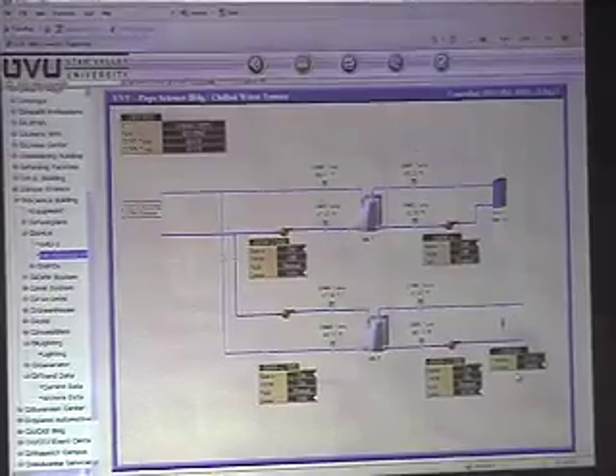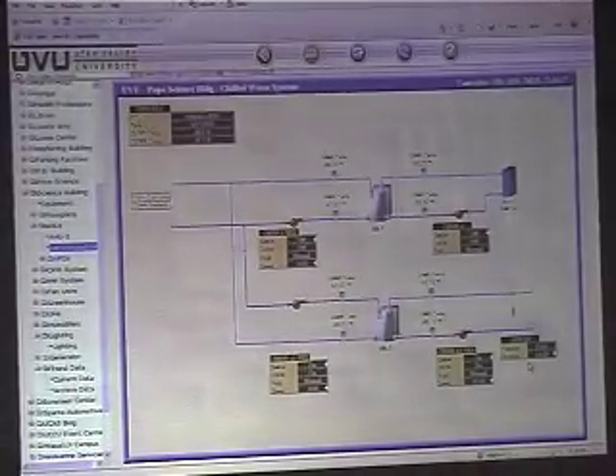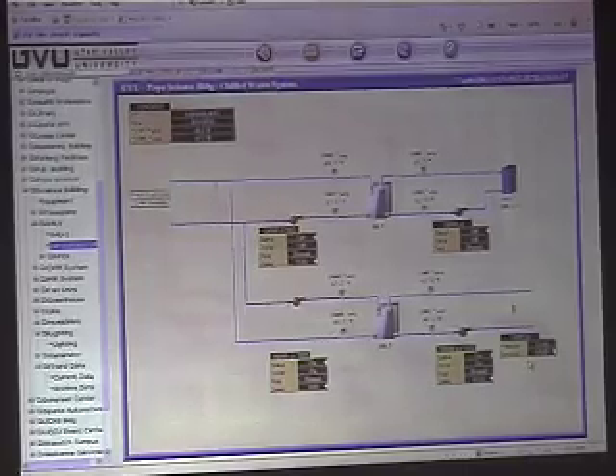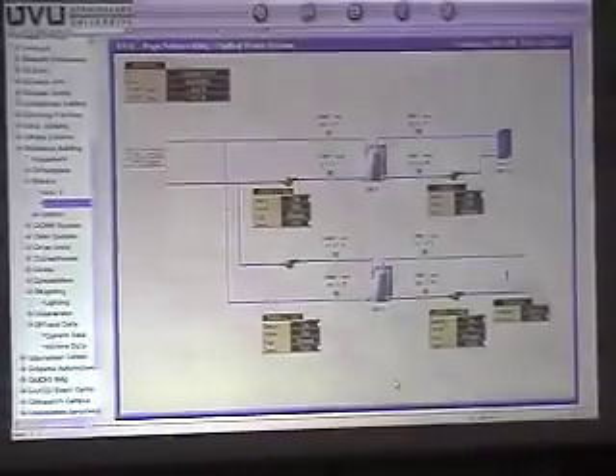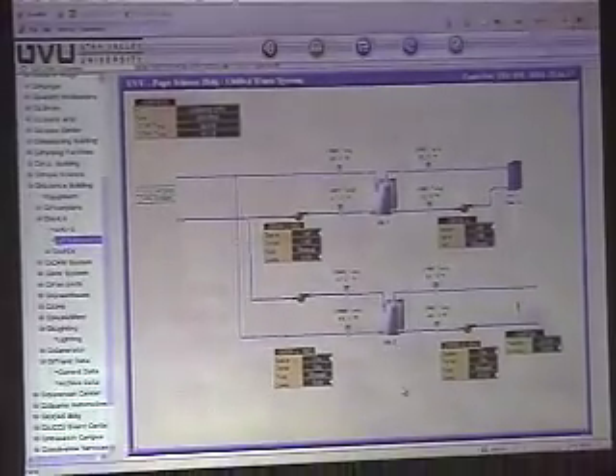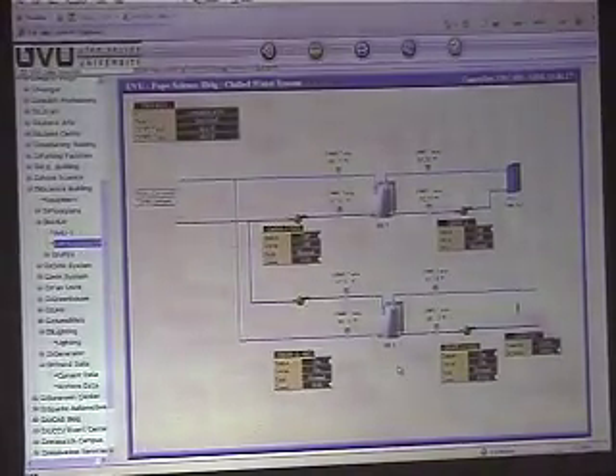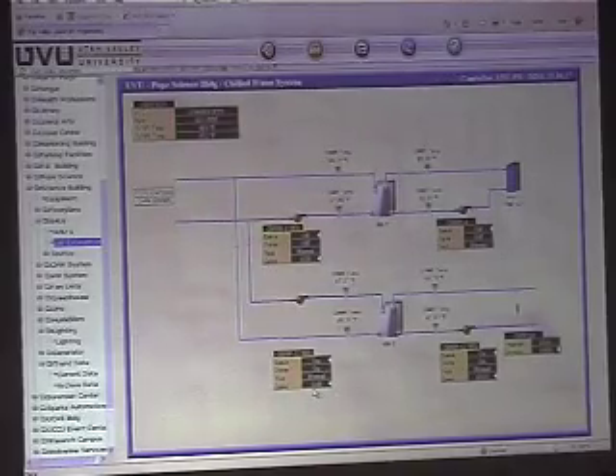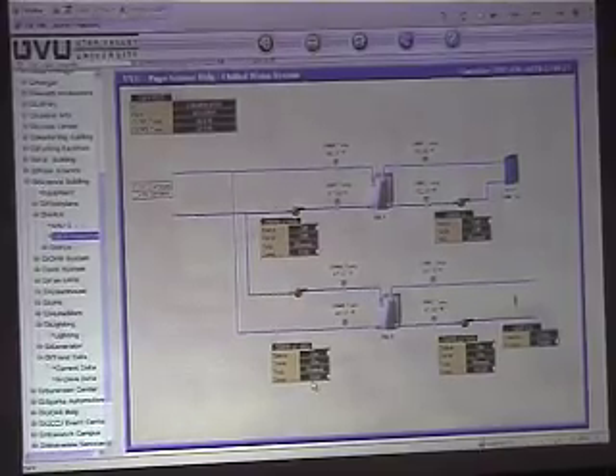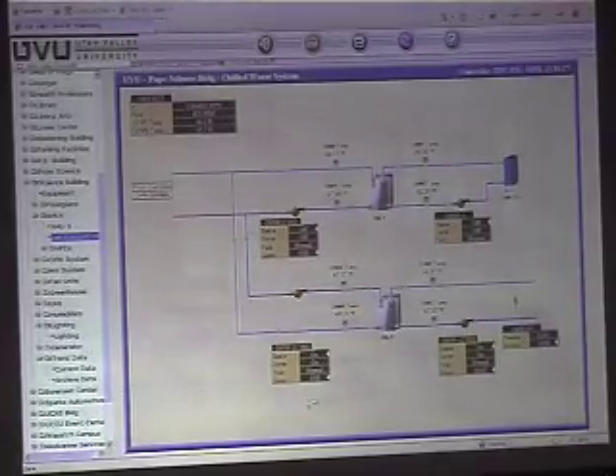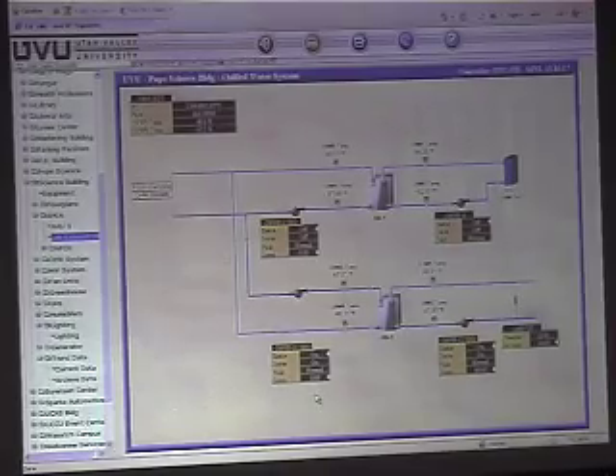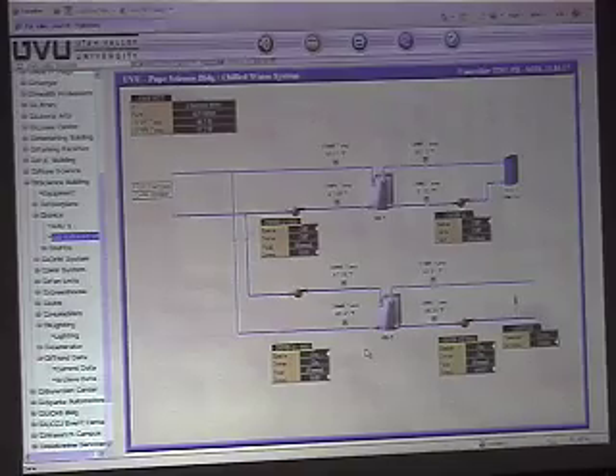In fact, the last time I was working with them on this, the equipment wasn't even installed yet, so I'm not sure if it's been installed yet or not. And does that pump, pump 11, ramp up and down based on the cooling demand for the secondary unit there? Yes, and I need to add a set point here once we figure out what that is. Oh, yeah. So we'll maintain the pressure to get the flow to all the equipment, and then we'll determine what temperature we need to maintain. So you've already got a loop set up for it in that programming? Yeah.